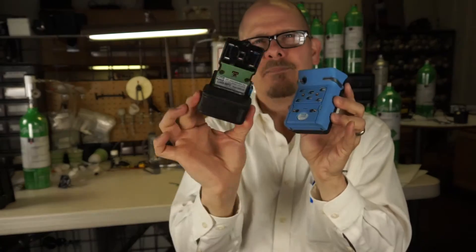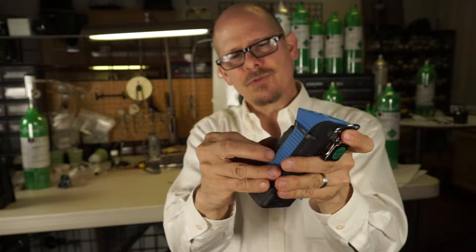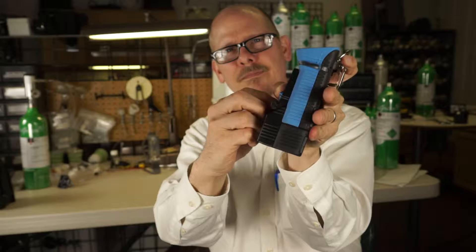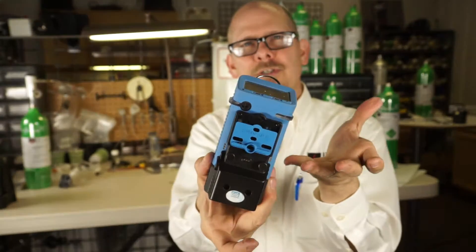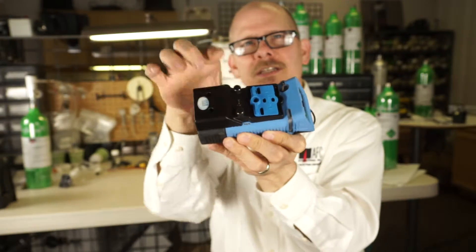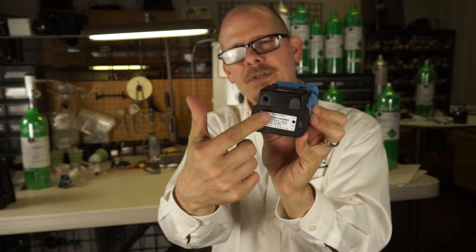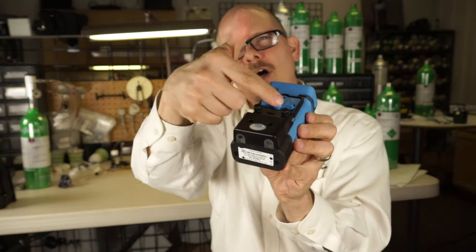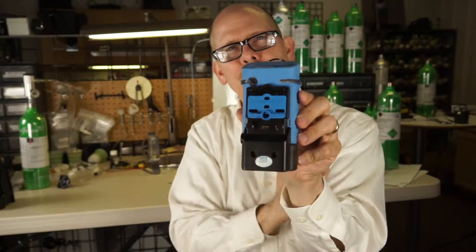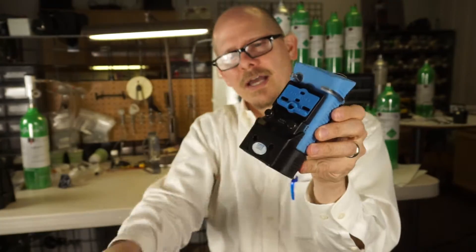However, you can run it with a pump. The pump is an attachable-type that screws onto the back of the unit with little thumb screws. Once attached, with the louver in the open position, you can use it as a diffusion unit. If you want to use the pump, push and slide that louver up — it closes off the diffusion ports and allows the pump to turn on. The entrance port to the pump is right here; air comes in, goes through a manifold system, and goes to all your sensors. We can go up to 80 to 100 feet of tubing, so we can pull from a long distance.